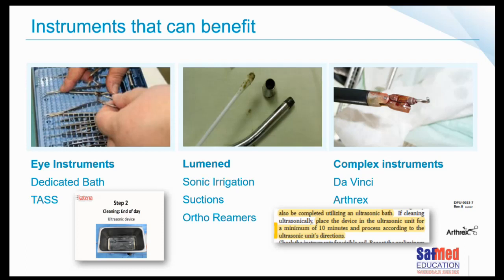Looking after your eye instruments is crucial, and they certainly benefit from ultrasonic cleaning. Other instruments that benefit greatly from ultrasonic cleaning with sonic irrigation are lumened instruments - anything with a relevant lumen that can go in an ultrasonic cleaner will benefit, such as suctions and orthopedic reamers, which are also quite difficult to clean. Again, consult the manufacturer's instructions for use.